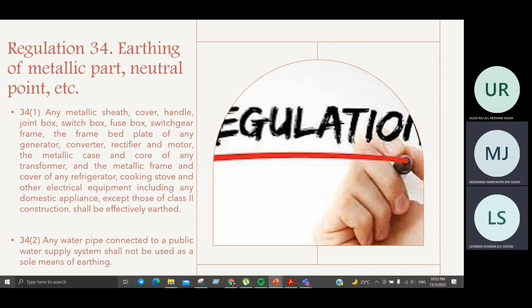So both cases are wrong based on regulation 34, earthing for metallic parts and neutral point, etc. Under regulation 34, sub-regulation 1, any metallic sheath, cover, handle, joint box, switch gear frame, the frame and bed plate of any generator, converter, rectifier and motor, the metallic case of the core of any transformer, and the metallic frame and cover of any refrigerator, cooking stove and other electrical equipment including any domestic appliance, except for those of class 2 construction, shall be effectively earthed, which means that any metal parts should be effectively earthed. And the second, regulation 34 sub-regulation 2: any water pipe connected to a public water supply system shall not be used as a sole means of earthing.